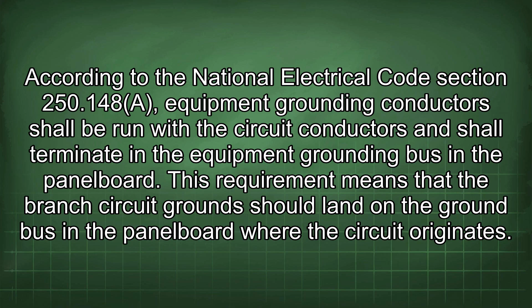According to the National Electrical Code Section 250.148(A), equipment grounding conductors shall be run with the circuit conductors and shall terminate in the equipment grounding bus in the panel board. This requirement means that the branch circuit ground should land on the ground bus in the panel board where the circuit originates.